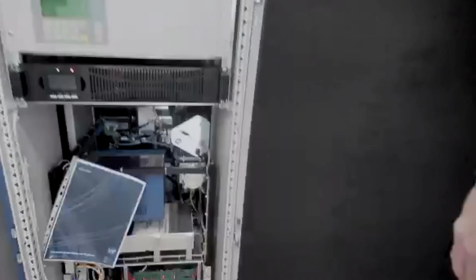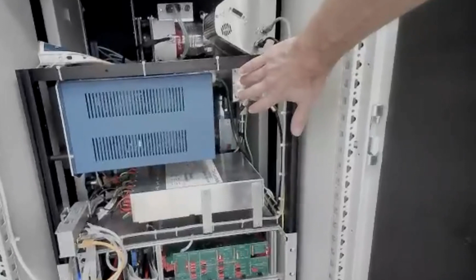Now to the big device. So you see here, it's a usual cabinet. You can open it on this side. On the inside, at the bottom, is the mass spectrometer. It's a little bit hard to see because it's all integrated. On the top edge, we have the vacuum chamber for the electron ionization mass spectrometer. The bottom chamber is for the IMR mass spectrometer.